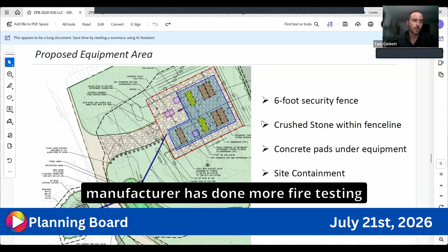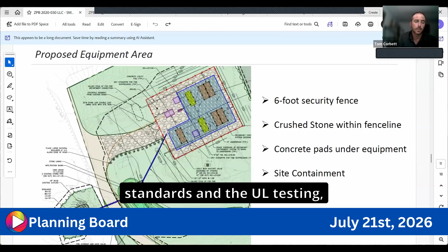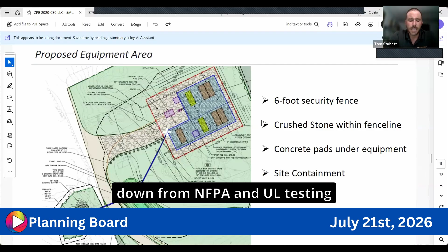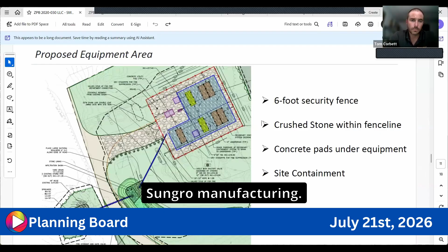That is correct. This particular manufacturer has done more fire testing and certifications than any other in the industry right now. They actually set fire to a system layout exactly like this - a whole full 5 megawatt system - and through UL standards and testing, the recommendations for site layout are what we're looking at here. This is drawn from NFPA and UL testing, provided to us by Sungrow Manufacturing. So this structural layout is industry standard for this particular system.